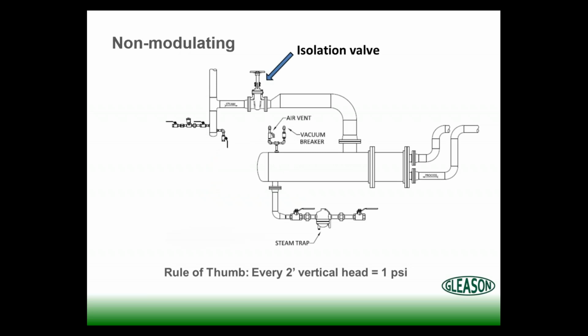Okay. When we're talking about steam traps, some best practices. The first thing we want to do when we're talking about heat exchangers, or really any application, is determine: is this a non-modulating or modulating application? A non-modulating application is one that does not control or vary the steam flow coming into the unit. In this case, we've got just an isolation valve feeding steam into the shell and tube heat exchanger, and here's our steam trap.